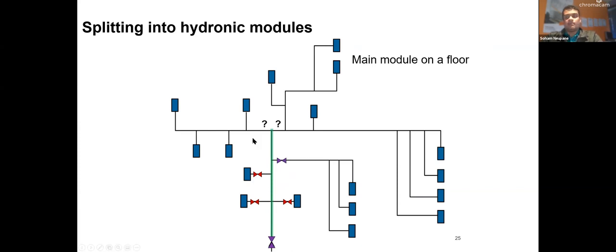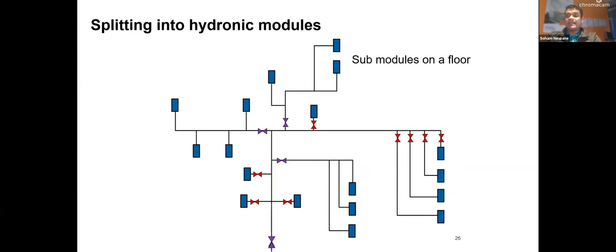And now we've reached another point here where we need to place a partner valve, right? So again, we've got many units on one side and many units on the other. Let's say this is where most of the flow is going since we have more terminals on this side. What you would do is you'd place a partner valve over here and then follow the main line again. And same thing here. Again, you have a partner valve going into these terminals. And each of these, as you can see, are individual terminals on there. And we place a manual balancing valve on each of them. So now we basically have a placement of some manual balancing valves, the final ones, as you can see in the red on your terminals, and partner valves installed, right?